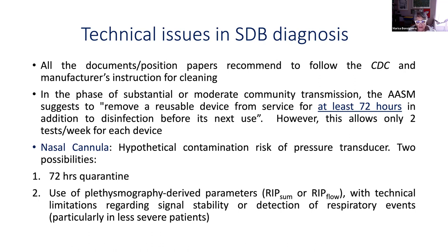There is a hypothetical contamination risk of the pressure transducer through the nasal cannulas. This is really hypothetical because the nasal cannula has no flow, so it only records pressure, nasal pressure. There are 2 possibilities. One is a quarantine for 72 hours, about which we've talked already. The other is to use no sensors on the face and use plethysmography-derived parameters. This is okay if the signals are good, but sometimes they are unstable, and that could be a problem for the detection of respiratory events, especially in less severe patients.